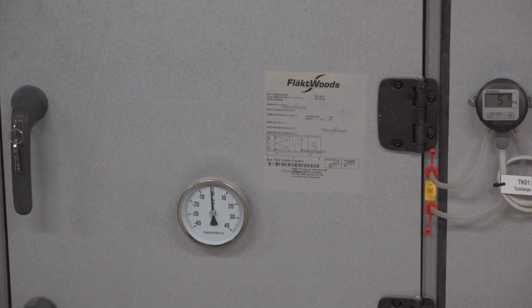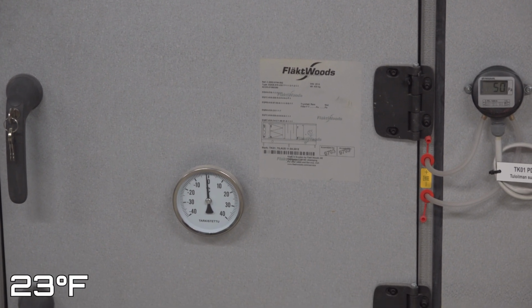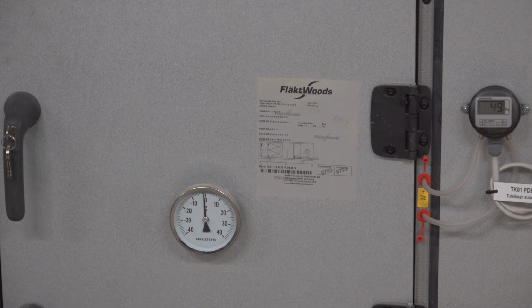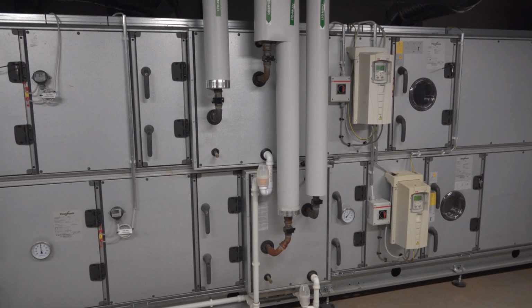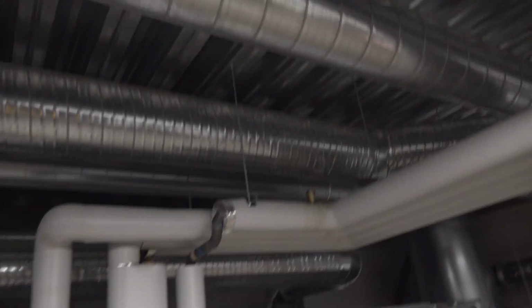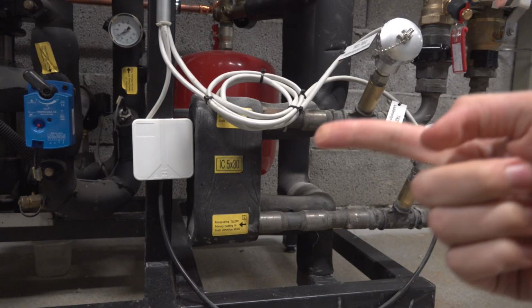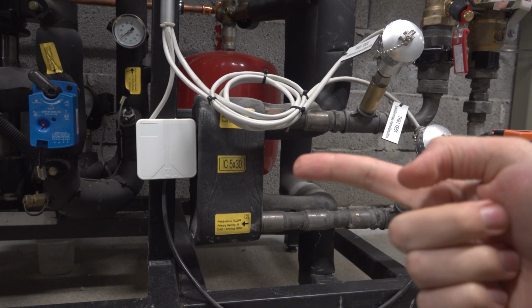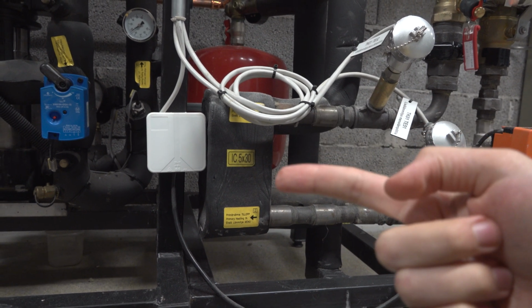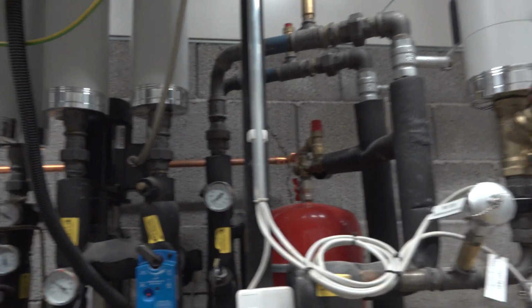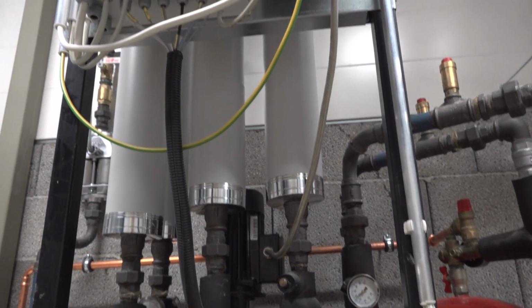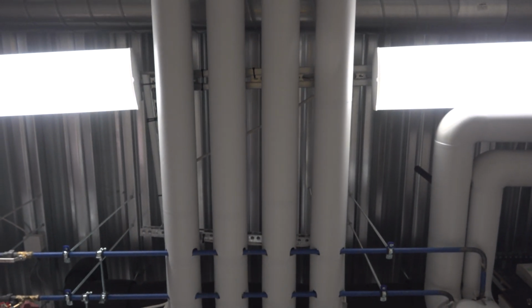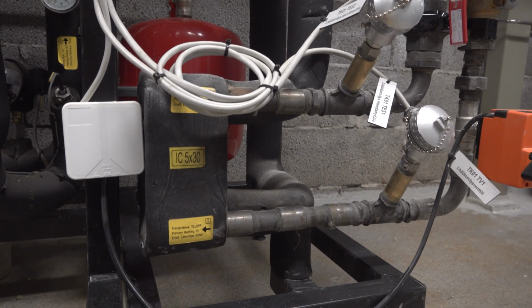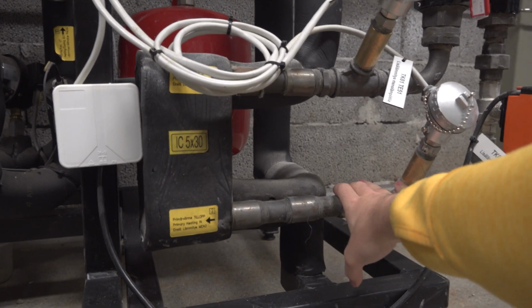In our building, if the temperature dips below minus 5 degrees Celsius, we need extra heat added into the heat exchanger circuit here. And how that happens is that we have a separate heat exchanger here that takes energy from our district heating and adds to that energy running in the loop. So it's basically being used to make the water in the tubes hotter. Currently we are not taking any energy from the district heating system, so the pipes are cold.